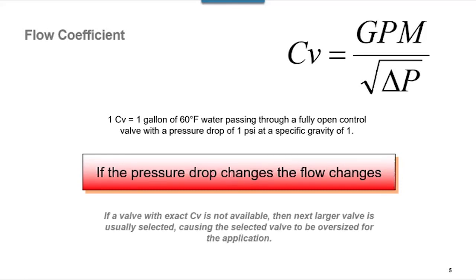Keep in mind, too, that the majority of control valves are oversized. I'm sure you know that from being out on job sites. I know that from sizing valves because there are only certain values of CVs for any particular valve.